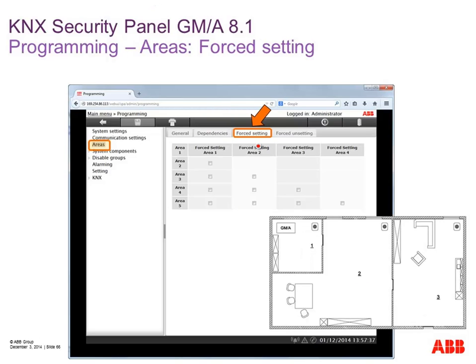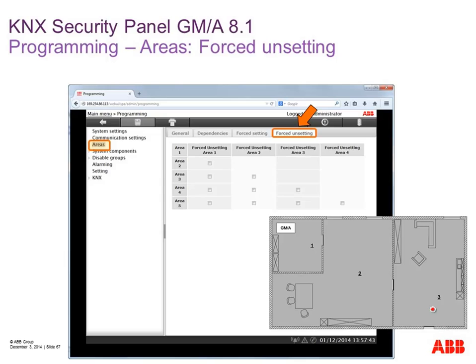A new feature inside the alarm logic is so-called 'force setting,' not possible with the former L240 system. With the same building having three areas, via force setting you go to area three and by setting area three, areas two and one are also set in one step — you tick the correct boxes for this forced setting. Vice versa: by unsetting area three when all three are set, you can also unset areas two and one in one step — you also tick the correct buttons for forced unsetting.